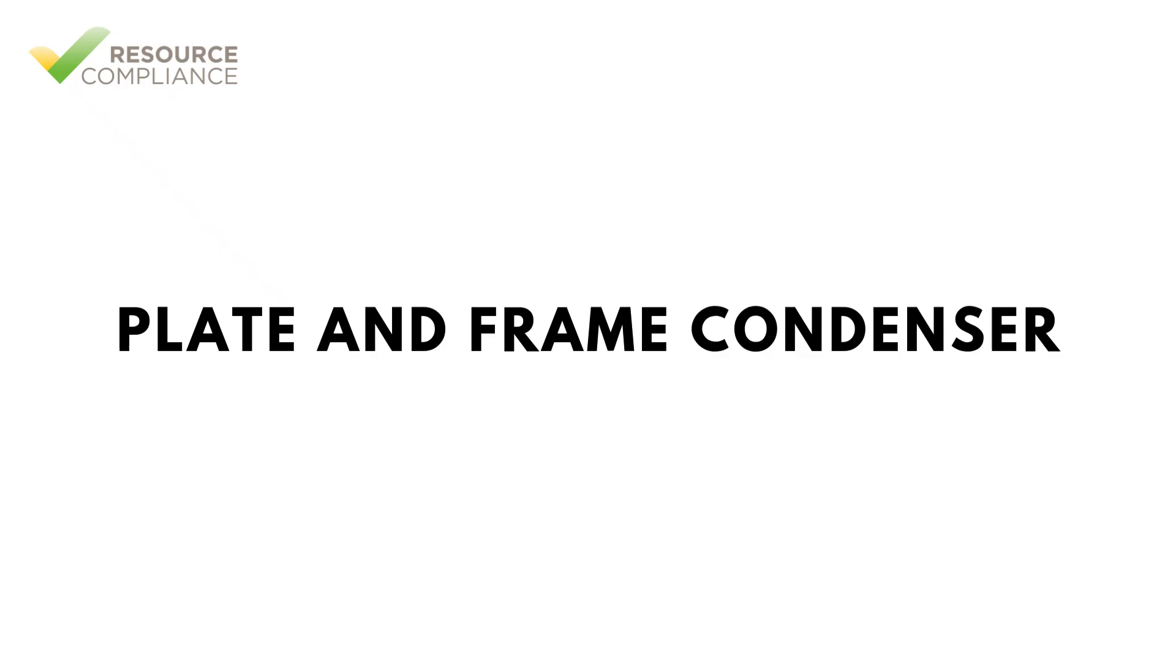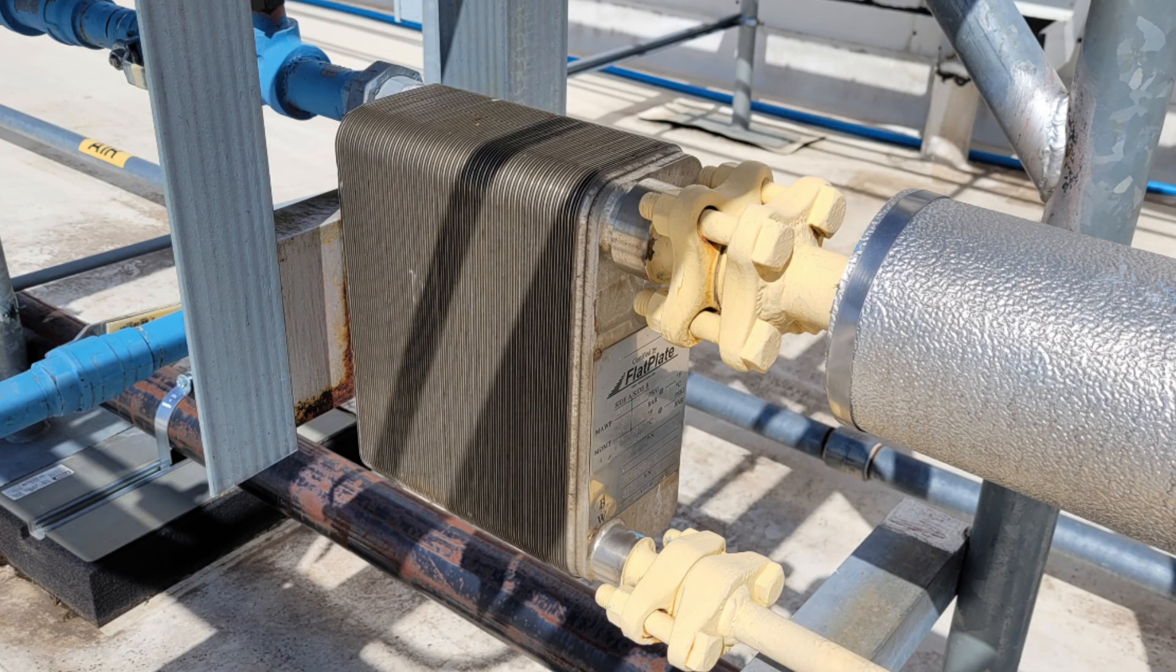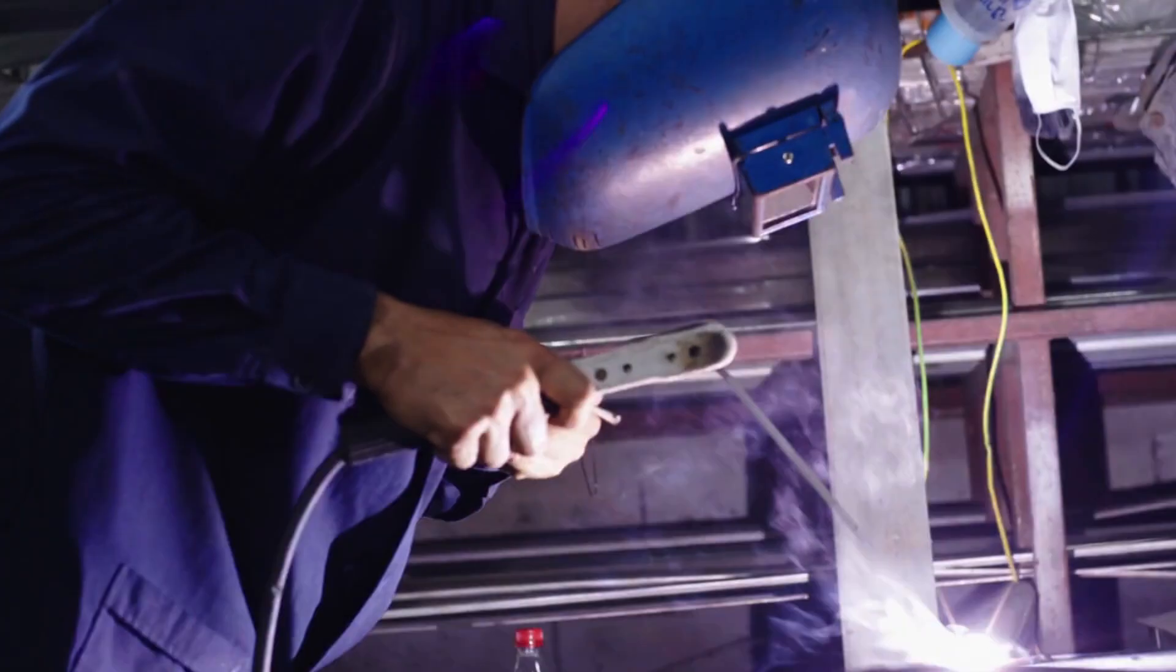A plate and frame condenser consists of a series of thin corrugated metal plates, typically made of stainless steel. Each plate has a gasket that seals the plate edges to ensure the fluids do not mix. Small plate and frame heat exchangers are often seal welded to negate the need of gaskets altogether.